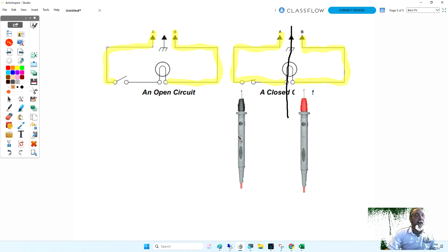So everything on this side is line 1, everything on this side is neutral. So when I put my meter lead on one side of the load and on the other side of the load, I'm going to have 120 volts as long as everything in my circuit is good. But if I move over to this one, because the switch is open, line 1 isn't coming this far in, I have to find out why my bulb doesn't work. And the first test I make is, do I have voltage to my light bulb?